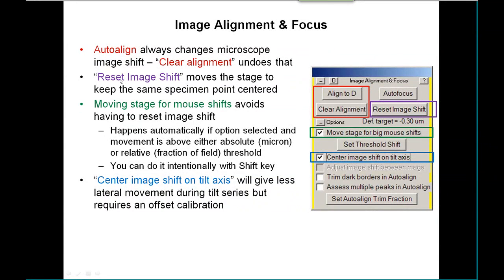The Reset Image Shift will clear out the image shift by moving the stage by a corresponding amount to try to keep the same specimen point centered. That's not perfect, because any time you move the stage, you lose a few tenths of a micron of precision in your positioning. Moving stage for big mouse shifts is a way to avoid having to reset the image shift manually as you make large movements over a number of microns.